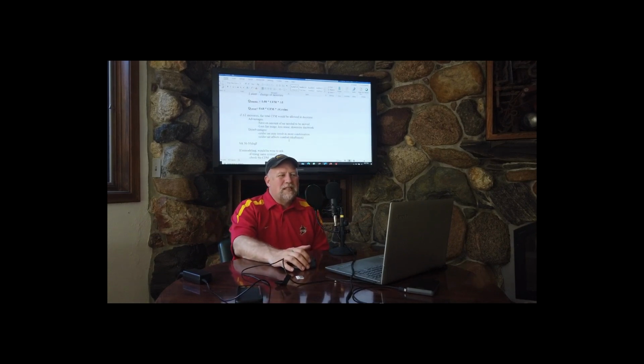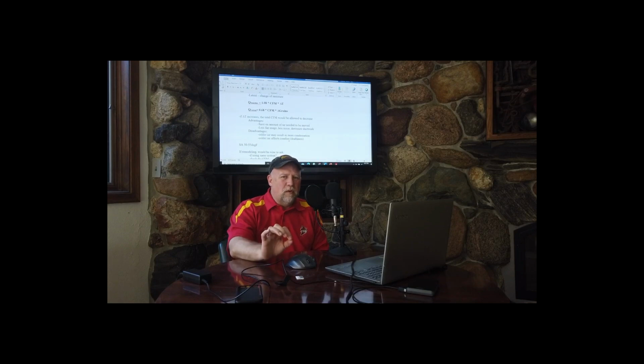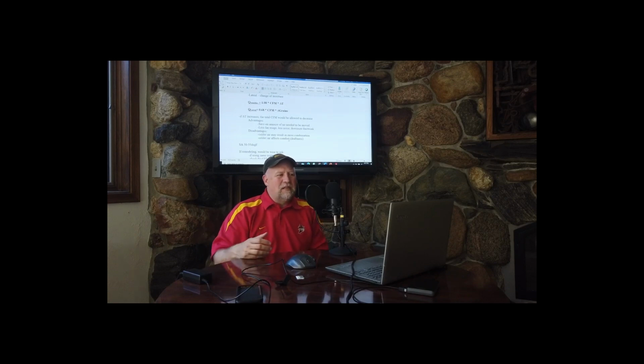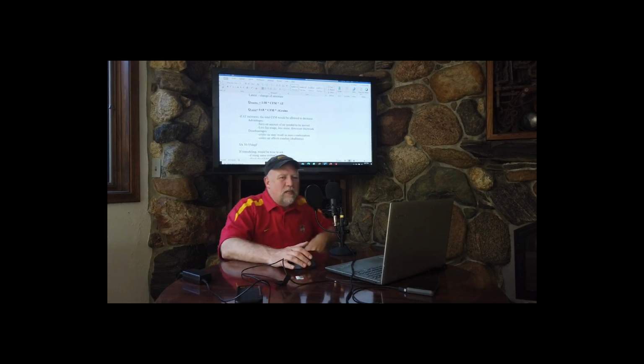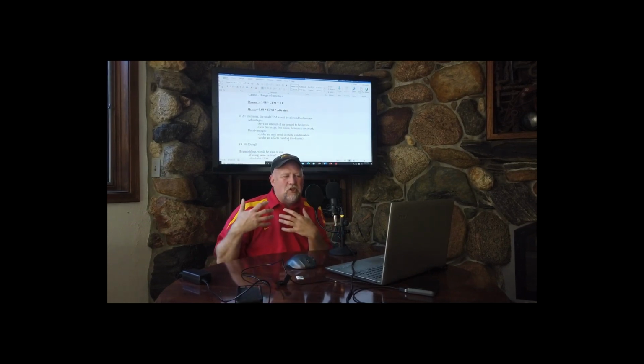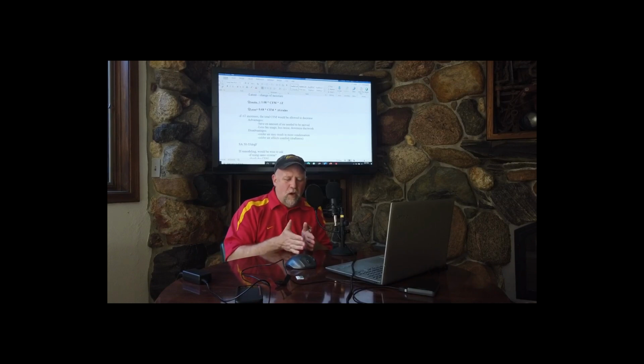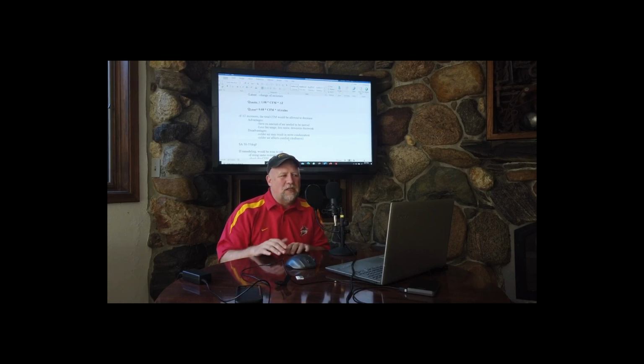If we are designing it from new, in other words, the building isn't built yet, I'm a design engineer and I'm going to design the mechanical systems, I'm going to choose the delta T. In other words, that is an engineer's choice. The engineer is going to pick, what is my space temperature? The engineer is going to pick, what equipment are we going to buy and what is the supply air temperature of the equipment that we're going to purchase?